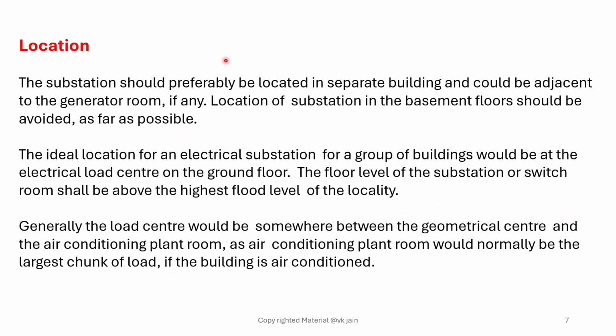It is very much necessary to decide the location of the substation at the design stage itself. The substation should preferably be located in a separate building, which could be adjacent to the generator room. Location of the substation in the basement floor should be avoided as far as possible.